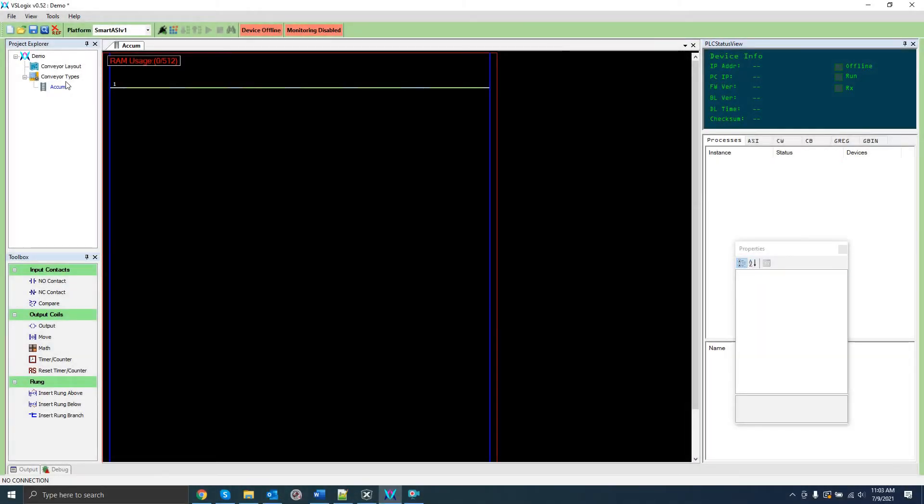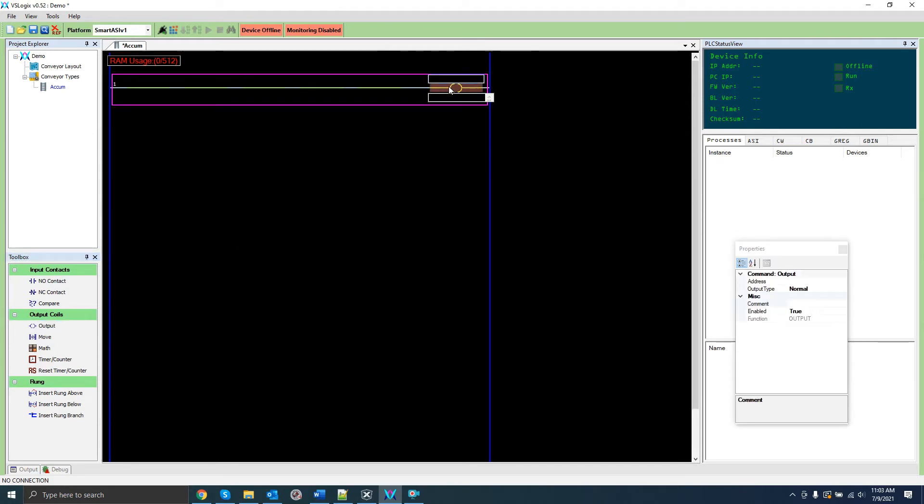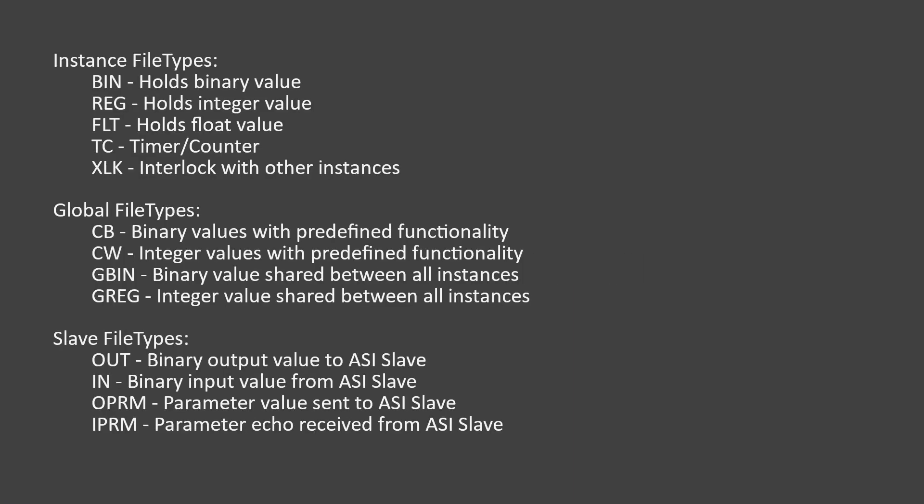The first thing I'm going to do is make the Ladder Program toggle an output on a slave. For that, I'm going to begin by putting an output coil on the rung here. This will alter a single bit, which is enough for the I/O we're going to toggle. Now, all contacts and coils need an address to know what data they're operating on. There are two required parts to an address, a file type and an index. There are 13 different file types in total. Each file type stores a certain type of data and is intended for a certain purpose. There are three subtypes of file type: instance, global, and slave.